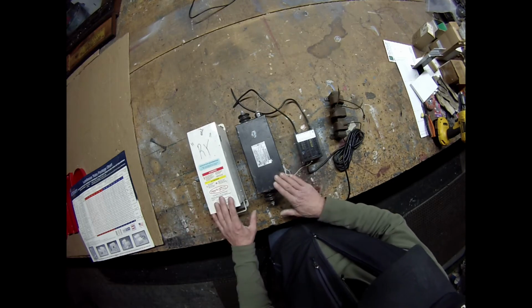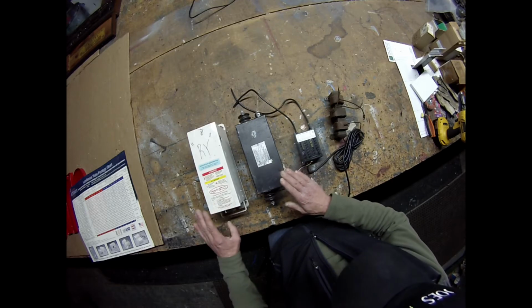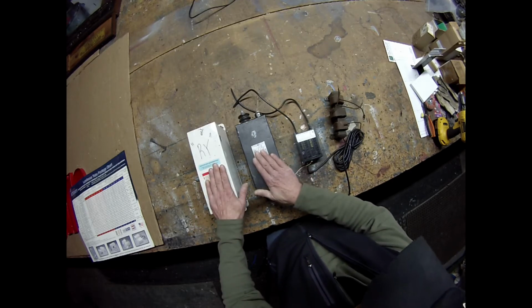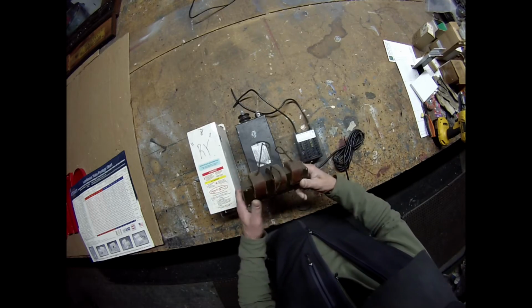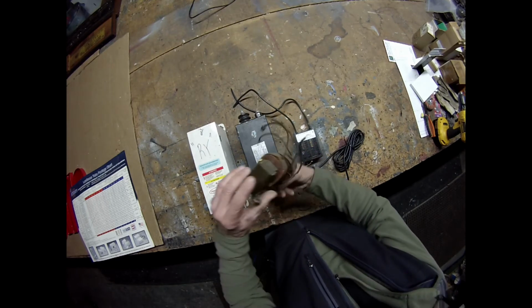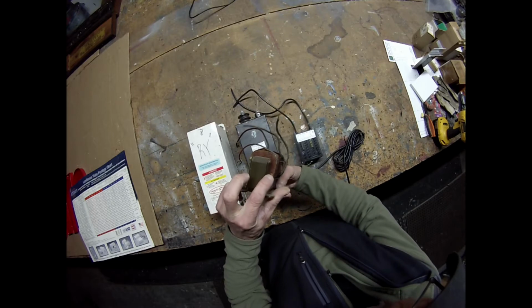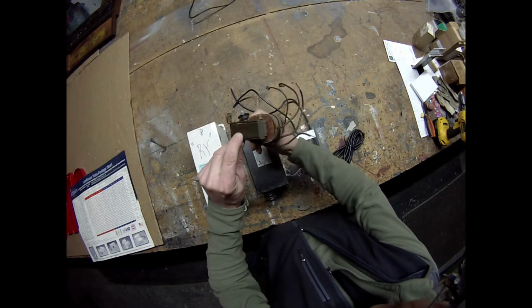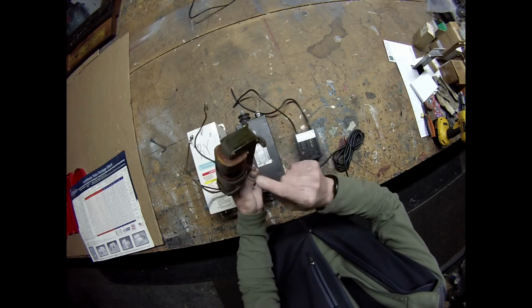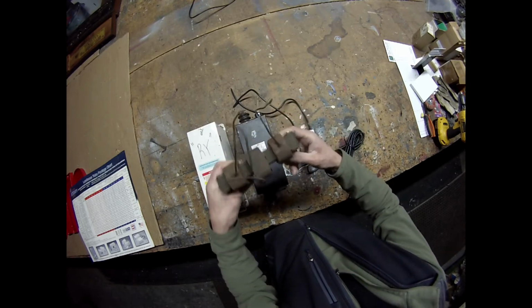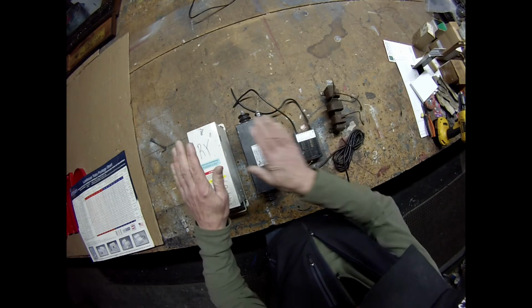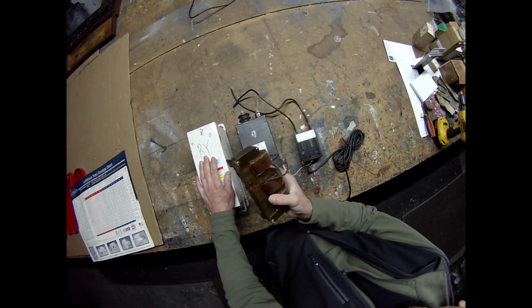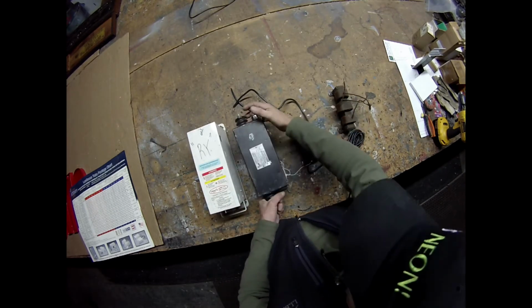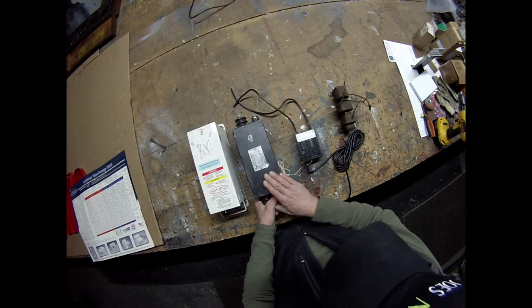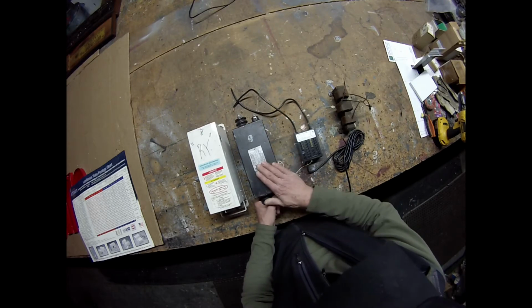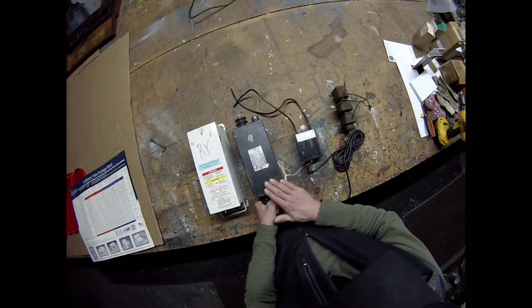These run off of a 110 or 120 volt circuit, okay? And inside of these transformers is what is called a core and coil. This is a core and coil. Basically what you have are slices, or should I say sheets, of steel that are all stacked up, and they're wrapped with these coils of copper wire. Okay, this is called a core and coil transformer. That's what makes these transformers real heavy. These are a standard transformer that would go in most of your exterior signage. Very common for exterior use.